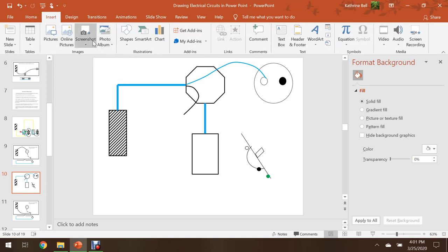So let's come in here now and let's draw our black insulated, ungrounded conductor from our source. I want to change that to black. I've got to get power down to my switch. National Electrical Code 200.7(C) states that the white insulated conductor may be used to carry power to a switch, but that it cannot be used as the return from the switch to the light.